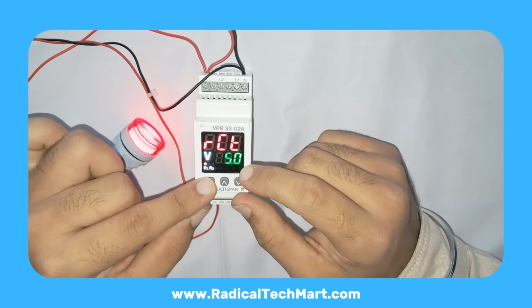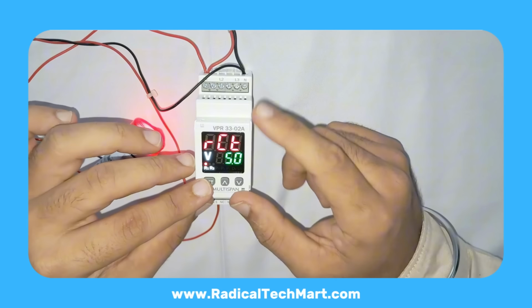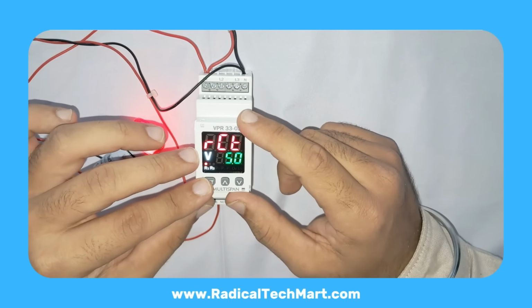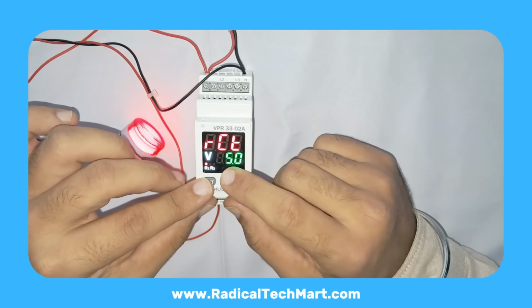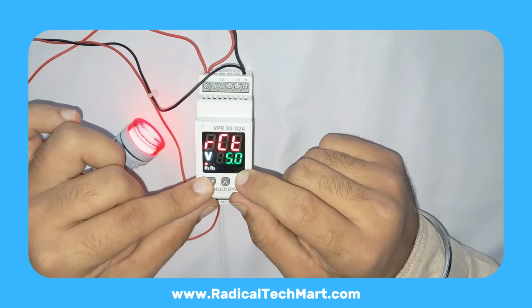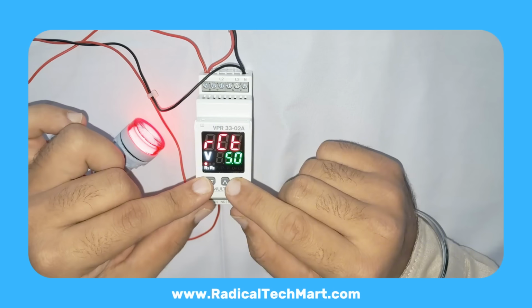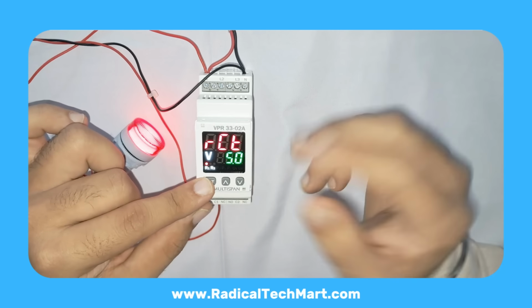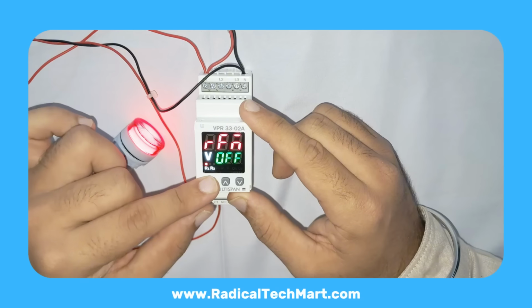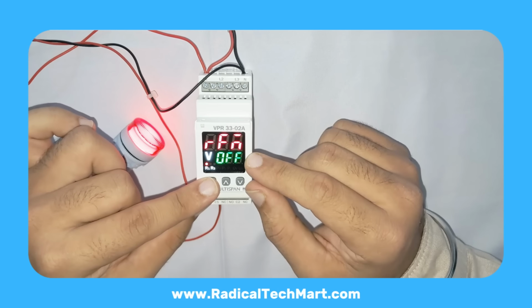When auto is selected, you get an additional parameter. Recovery time, default is 5 seconds. That means after the voltage becomes healthy again, the relay will turn on automatically after 5 seconds. Press Set. Next is relay fault mode.